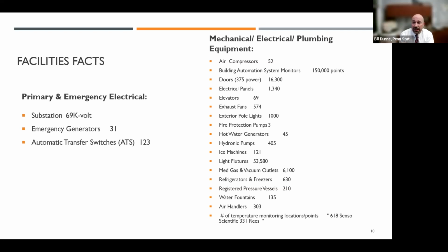Pressure monitoring is another one. We also have positive pressure, used in areas like oncology or surgical environments where we want really clean areas. We don't want air from outside or the room coming in, so we bring in fresh air, filter it through HEPA filtration, chill or heat it, or humidify it, then push it into the room. That creates a positive relationship to the hallway, corridor, or neighboring room, so we don't suck any dirty air into that environment.